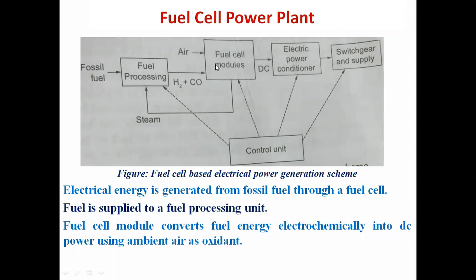There is a control unit which controls the amount of fuel supplied to the fuel cell module and overall controls the activity of all four blocks: fuel processing unit, fuel cell module, electrical power conditioner, and switchgear and supply. Electrical energy is generated from fossil fuel through hydrogen: fossil fuel is converted into hydrogen, hydrogen is supplied to the fuel cell, and electricity is generated. The fuel cell module converts fuel energy electrochemically into DC power using ambient air as oxidant, and then the inverter converts DC to AC.